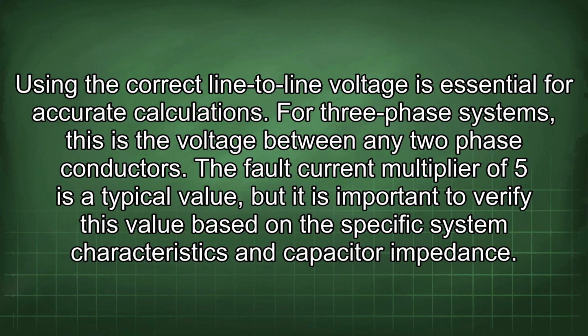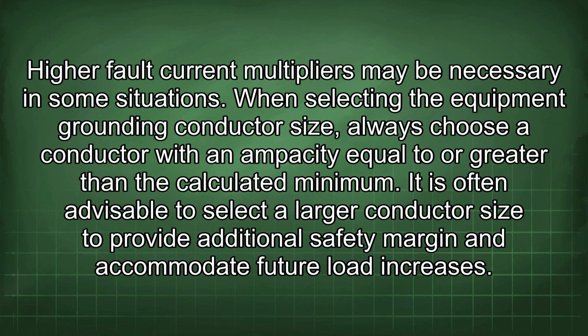The fault current multiplier of 5 is a typical value, but it is important to verify this value based on the specific system characteristics and capacitor impedance. Higher fault current multipliers may be necessary in some situations. When selecting the equipment grounding conductor size, always choose a conductor with an ampacity equal to or greater than the calculated minimum. It is often advisable to select a larger conductor size to provide additional safety margin and accommodate future load increases.